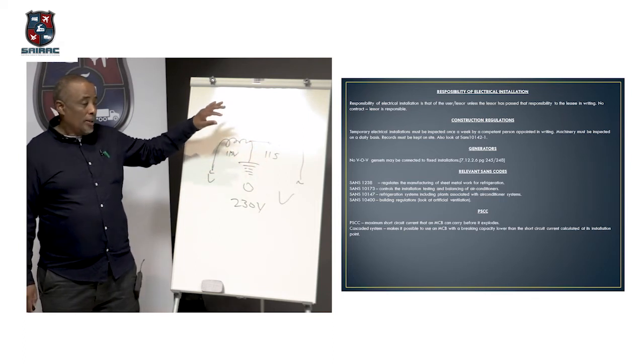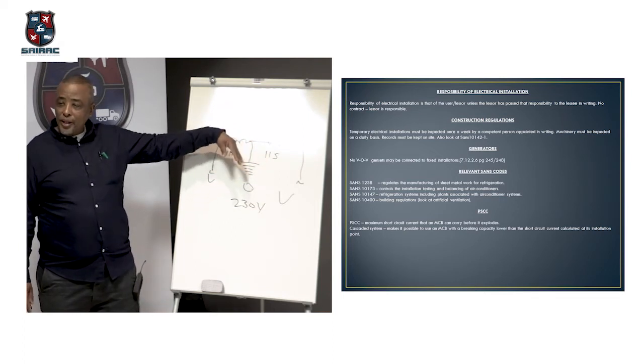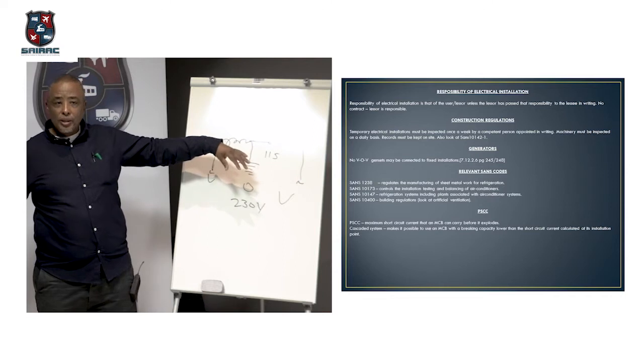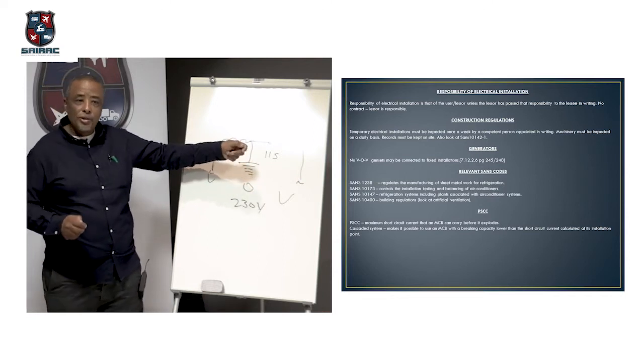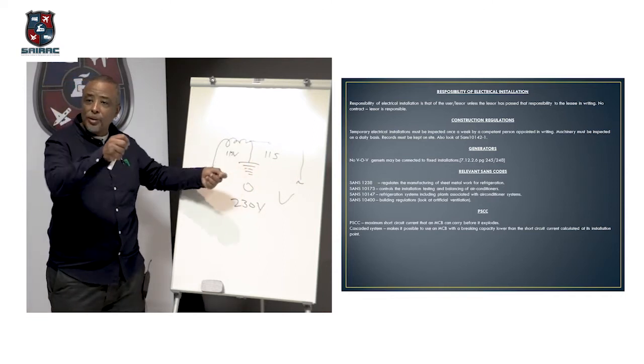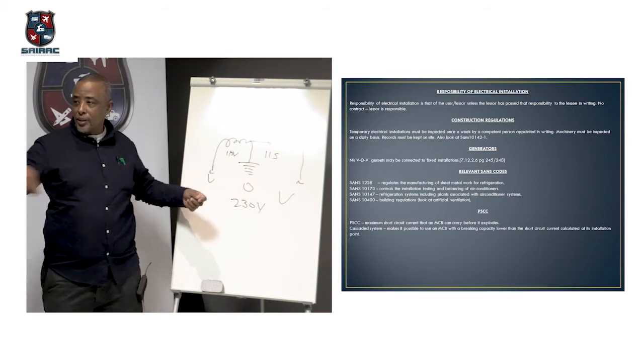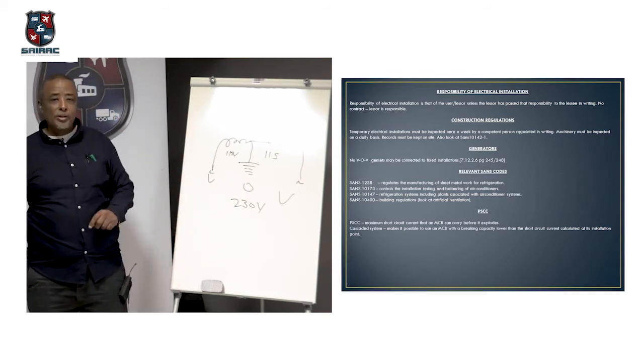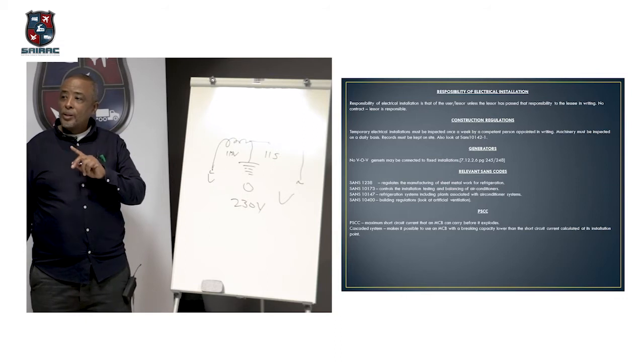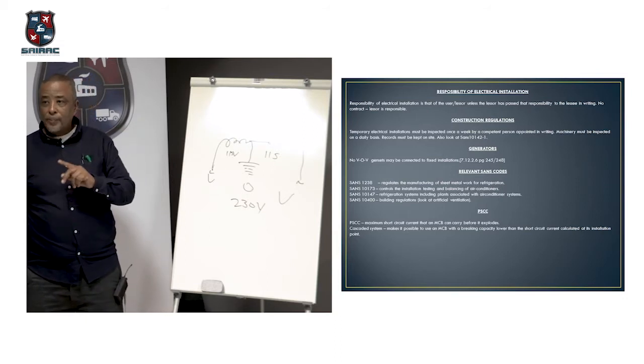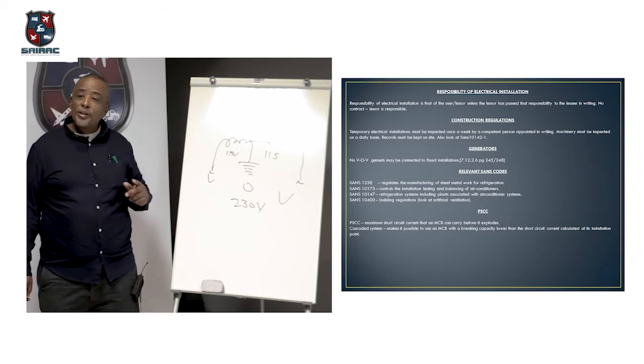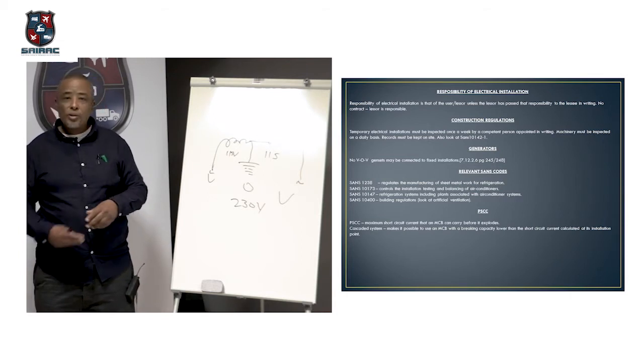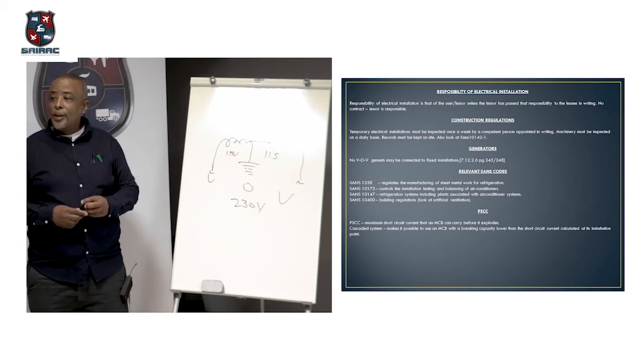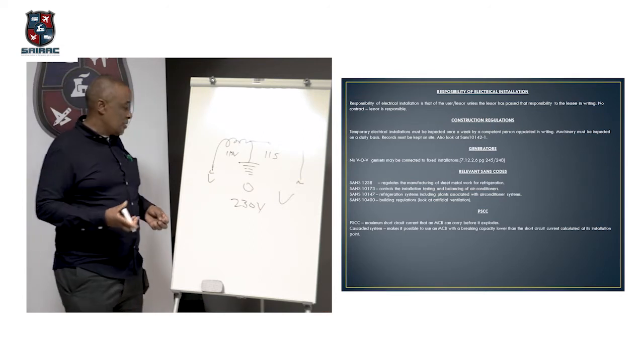Okay. The way to test it would be to test from an incoming neutral and an external earth. Not your earth and your neutral in the house. It's an external earth. Knock an earth spike in outside or something, and you'll find that your voltage, if it's elevated, is at a dangerous level. Sometimes it's beyond your control. You can walk through the house and you can't find a problem. But this is what SANS says.